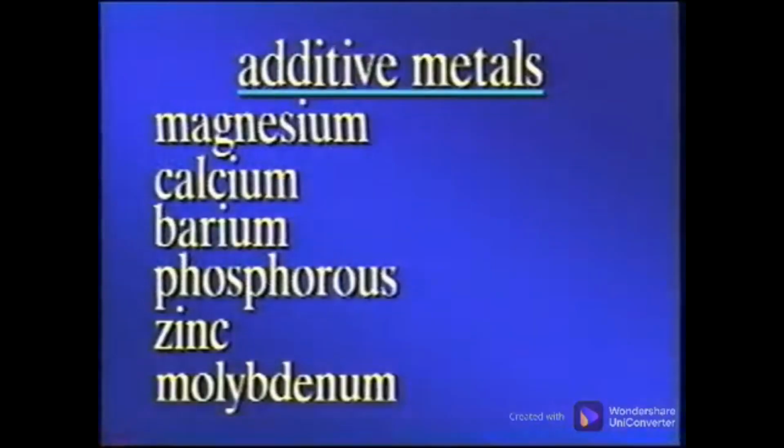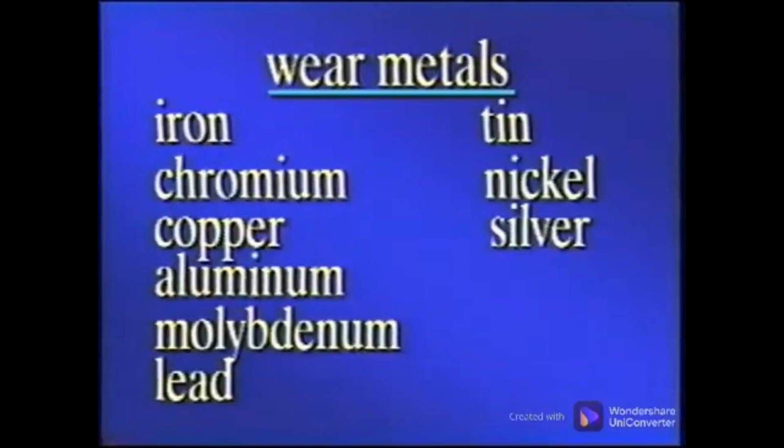make up the additive package and trending it over the sample periods. Common additive metals are magnesium, calcium, barium, phosphorus, zinc, and sometimes molybdenum. Wear metals detected are iron, chromium, copper, aluminum, molybdenum, lead, tin, nickel, and silver.